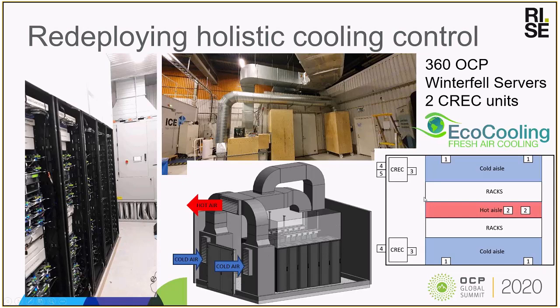In contrast to Boden, we have a contained hot aisle rather than a contained cold aisle, so a slightly different configuration. The whole data center becomes the cold aisle, and therefore we had to build some ductwork in the ceiling for the two extract fans to mix the hot air back with the coolers, or to reject the hot air out of the pod. Obviously, we don't want to reject the hot air into the outside room, so we're ducting it away, and this gives us the ability to measure the amount of heat that is available for the heat reuse calculations that we are doing as part of some other experiments. The two boxes that you see in front of the coolers, attached to the cooling units, are climate boxes, which allow us to dial in the climate, as part of another set of experiments.